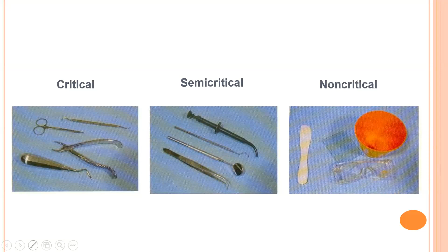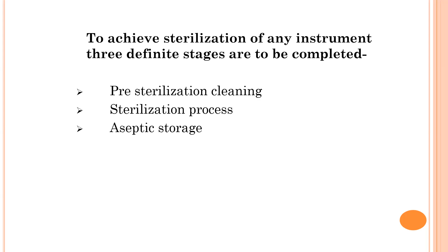So to achieve sterilization of any instrument, we need to have 2 or 3 processes that are involved. The first process is cleaning. So I told you in the beginning itself, what is cleaning? Cleaning is like you clean only the soiled parts. Any visible soiling, any visible dirt on the instruments has to be cleaned. So that is pre-sterilization cleaning. The second process is sterilization. And the third one is after sterilization, you should not expose the instrument to the outside environment until it is used on a patient. So you have to store it in a safe place, and this we call aseptic storage.